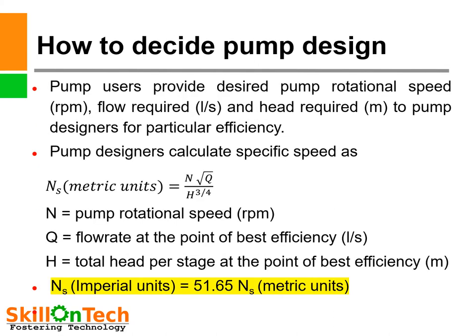Pump users generally provide the desired pump rotational speed in RPM, flow required in liters per second, and head required in meters to pump designers for a particular efficiency. Pump designers calculate specific speed as: Ns (metric units) = N × √Q / H^(3/4), where N is pump rotational speed in RPM, Q is flow rate at the point of best efficiency in liters per second, and H is total head per stage at the point of best efficiency in meters. Specific speed in imperial units equals 51.65 × Ns in metric units.